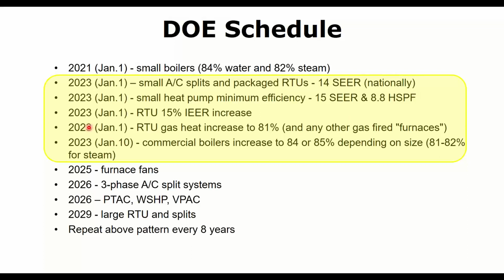On bigger stuff, for example packaged rooftop units, there was a 30% increase requirement in IEER, and that was split: 15% of that had a deadline of 2018, and the other 15% is 5 years later, which is 2023. So we're ready for that next 15% bump in IEER - part load efficiency. Also at that same time, the gas efficiency minimum is going to increase, although it's only going up to 81%, which is not very difficult to do, so that should not be very challenging for most manufacturers - that should be an easy one.